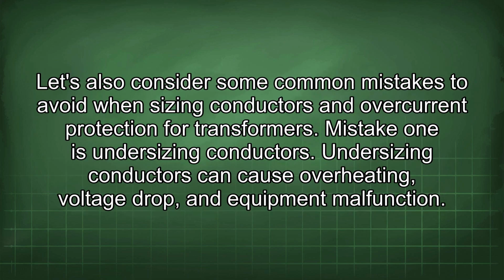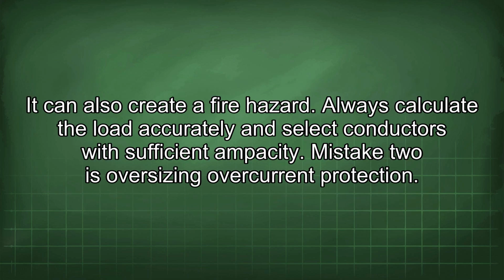Let's also consider some common mistakes to avoid when sizing conductors and overcurrent protection for transformers. Mistake 1 is undersizing conductors. Undersizing conductors can cause overheating, voltage drop, and equipment malfunction. It can also create a fire hazard. Always calculate the load accurately and select conductors with sufficient ampacity.